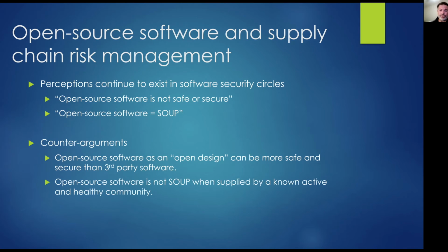Open source software is not SOUP when supplied by a known, active, and healthy community. If you have an active, healthy community, that community is a single source entity. You just have to make sure that that community is healthy and active and able to interact with the users of the software in an effective way.